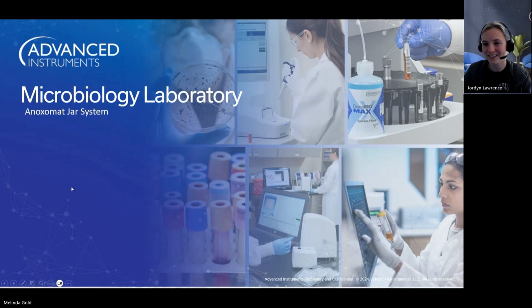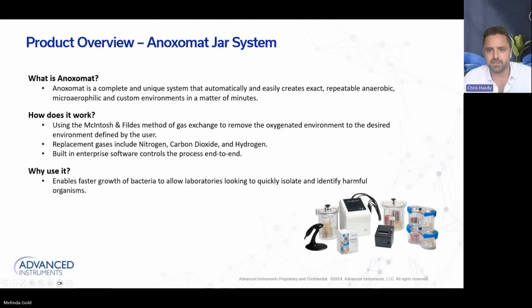So as Jordan mentioned, we're in the microbiology lab right now. So we're going to talk about the Anoxomat jar system. We're talking about anaerobes, campies, capnophils, all that good stuff. So a little product overview here. What is Anoxomat? Anoxomat is a device that utilizes a nitrogen, CO2, and hydrogen gas mixture to create anaerobic, microaerophilic, and other custom environments in a matter of minutes.